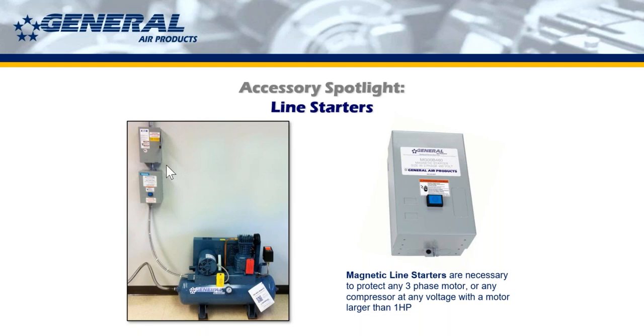So any three-phase unit that you put in is going to require one of these. And any compressor with a motor larger than 1 horsepower. So for us, that'd be 1.5 and up. We do a 1.5 horsepower unit up to 5. I think we do a couple units that are 7 horsepower. Anything single phase that's above 1 horsepower is going to need a line starter. And anything three phase, any size, is going to need a line starter.